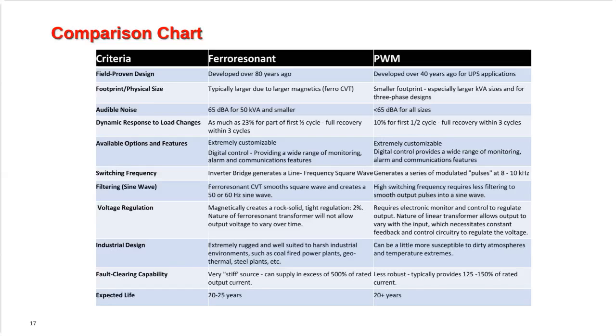Fault clearing capability: the Ferroresonant design of UPS is just excellent at clearing faults. It's what we call a very stiff source and can supply in excess of 500% of the rated output current of the system for a small amount of time to allow you to clear faults on the load circuits if necessary. For a PWM system, it's less robust. Typically, it's 125 to 150% of rated current. Now, don't get overly concerned about that. That doesn't mean that your fault isn't going to be cleared.